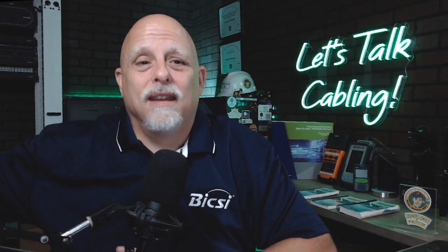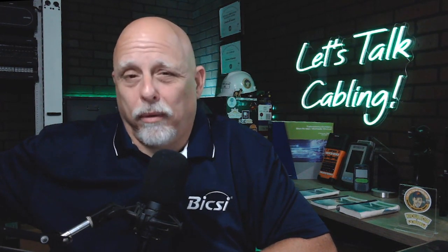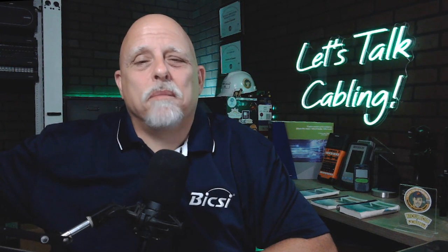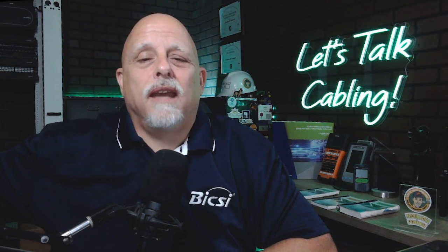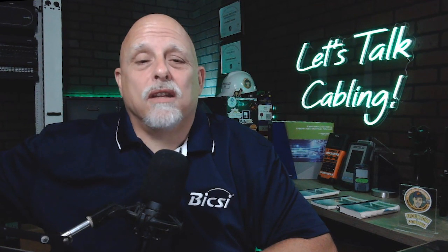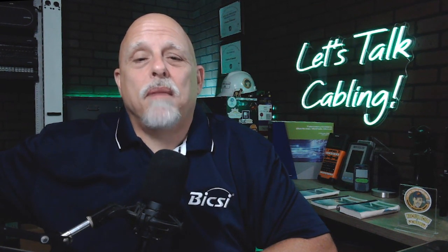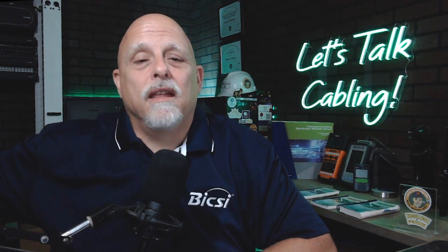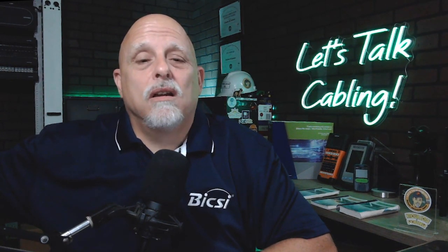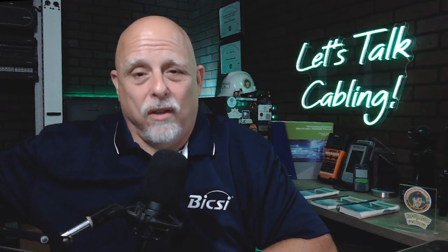The issue is, how well have you maintained your crimper? So let's talk about the impact on MPTLs. The choice between the pass-through and the traditional connectors can impact the performance and reliability of the MPTLs. Pass-through connectors are often easier, but they may introduce a variability if not terminated correctly. Traditional connectors require more skill, but they can provide more consistent results.